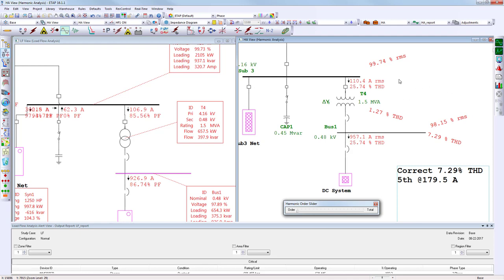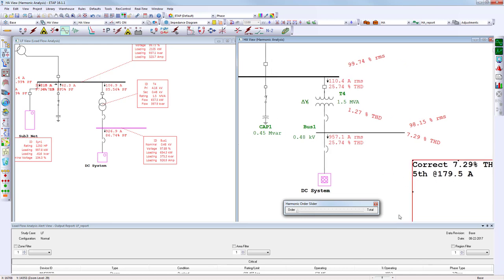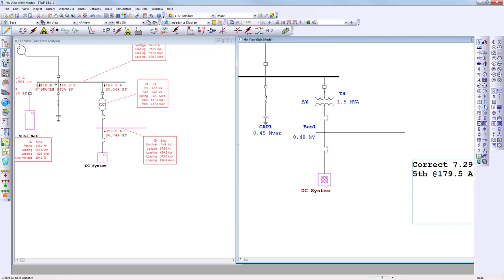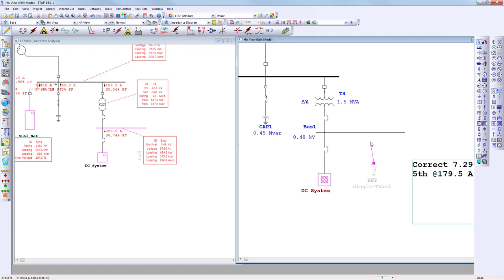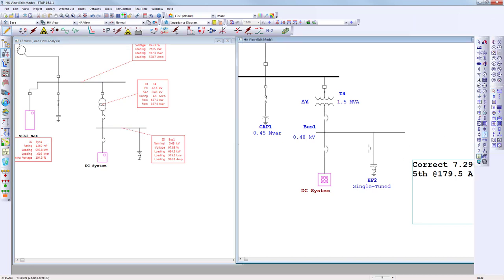Moving on, I'd like to size a harmonic filter. Switching to edit mode, I'll add a harmonic filter and attach it to the one-line diagram. When attached on the right-hand side it automatically appears on the left as well, since we're using the same database. I'll also add a circuit breaker. Under normal configuration, the circuit breaker should be set to open since this filter hasn't been commissioned yet — we're only performing a study.